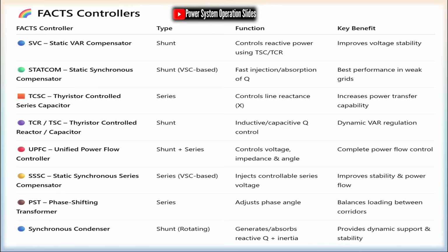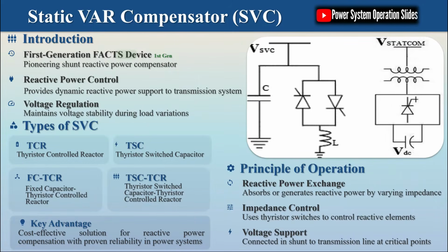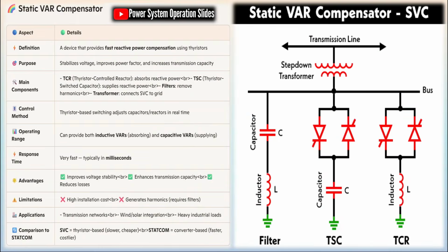This voltage-independent characteristic of STATCOMs provides a significant advantage during low-voltage conditions, as they can maintain their full reactive current capability even when the system voltage drops. Additionally, STATCOMs typically have faster response times, often less than 1 cycle, compared to SVCs, typically 1 to 2 cycles, making them more effective in mitigating rapid voltage fluctuations and improving transient stability. The VSC-based topology also allows for more precise control of reactive power and can be designed to have a smaller physical footprint than equivalent SVCs.